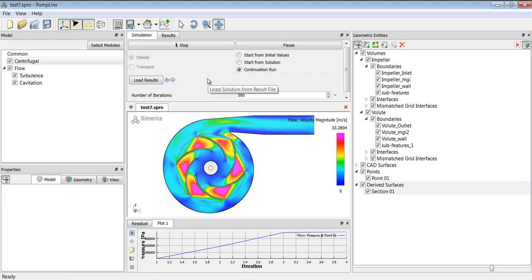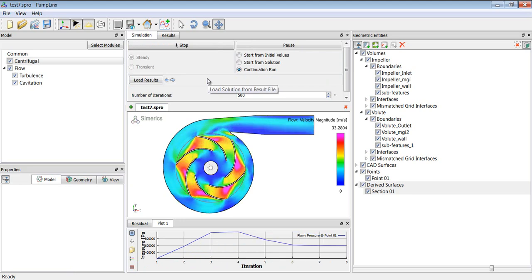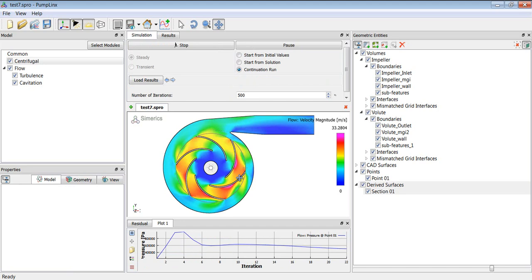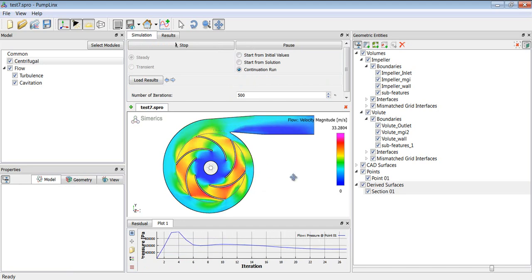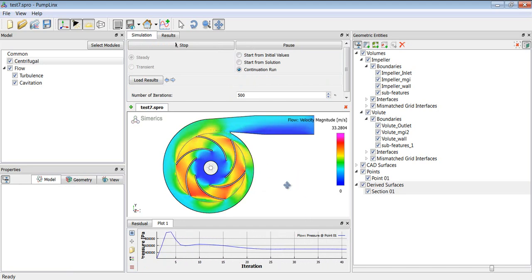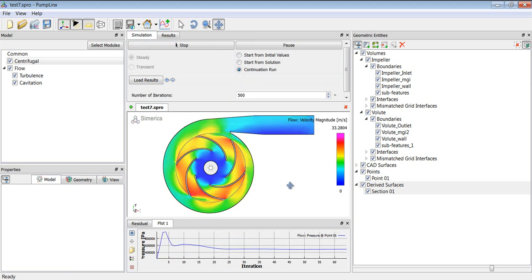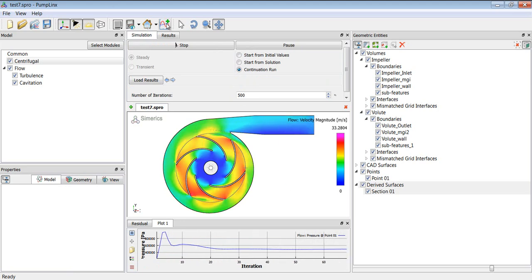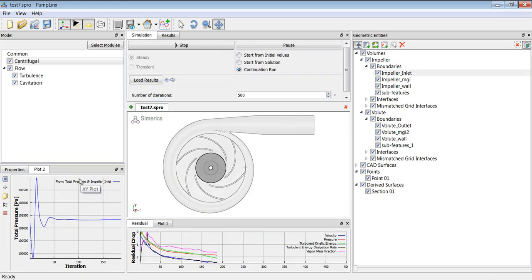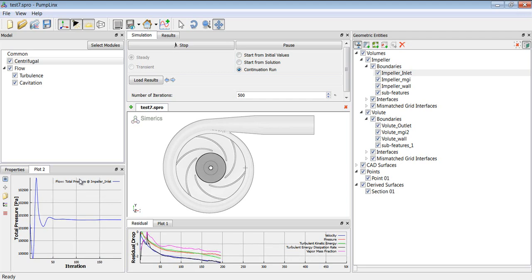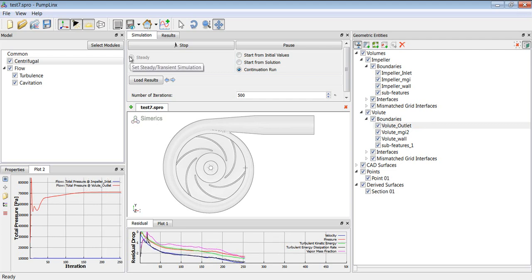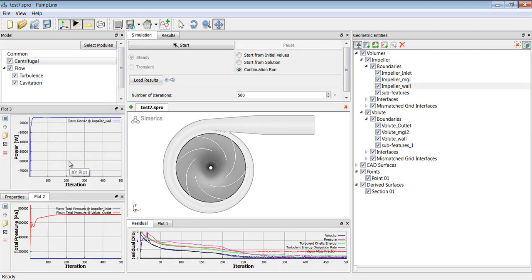And here we've launched the solver. And you can see the velocity field beginning to take shape. And here we're monitoring the pressure at the periphery of the blades. And you can see the pressure is starting to stabilize and becoming linear, which means that the solution is converging. Go ahead and put in a couple more plots. Here we have the pressure at the inlet. And let's add pressure at the outlet so that we can compare both pressures. And then we'll know the pressure difference across this device. And here is the pressure at the outlet in red. I'll add one more plot. And here we have the power that's required to run this pump.